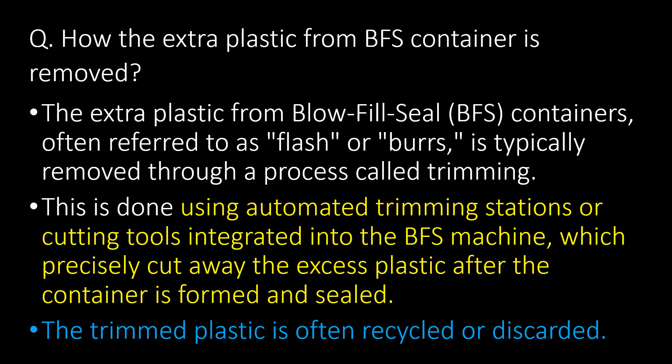How is the extra plastic from BFS containers removed? The extra plastic from blow-fill-seal containers, often referred to as flash or burrs, is typically removed through a process called trimming. This is done using automated trimming stations or cutting tools integrated into the BFS machine, which precisely cut away the excess plastic after the container is formed and sealed. The trimmed plastic is often recycled or discarded.